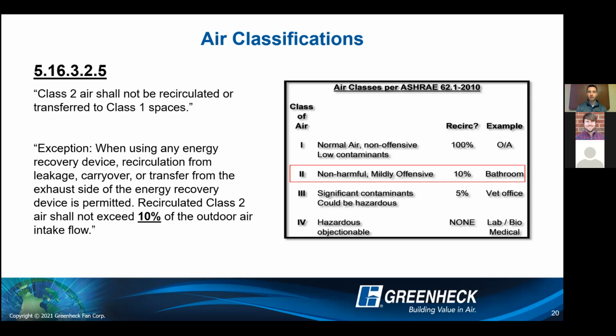Number 2, or I should say air classification 2, would be mildly offensive smell. It's not really harmful. Think about your toilet or your bathroom type exhaust systems. Up to 10% recirculation or cross contamination is allowed. When you get into class 3, that's where up to 5% recirculation is allowed. That is where you're looking at more significant contaminants. They could be hazardous. They could smell a little bit more. So think about your nail salons, your dry cleaners, barbershops, vet offices, things like that. But up to 5% is allowed.